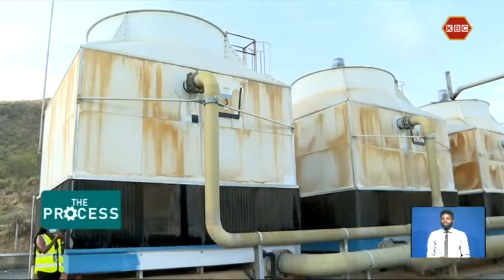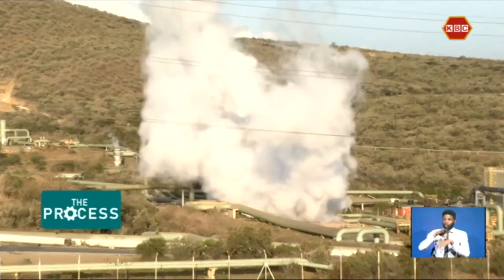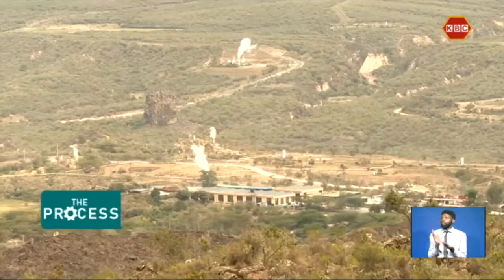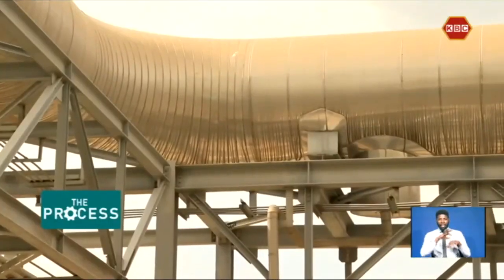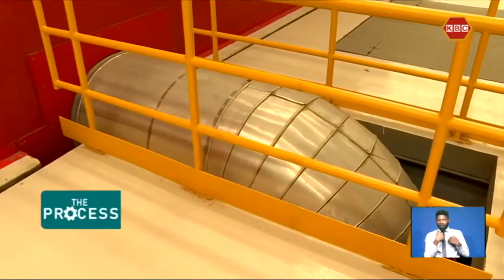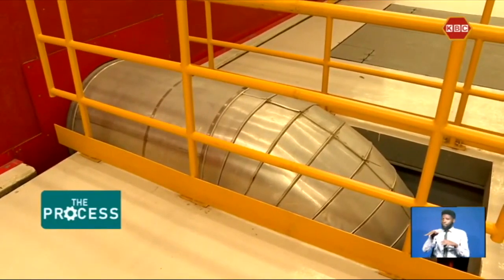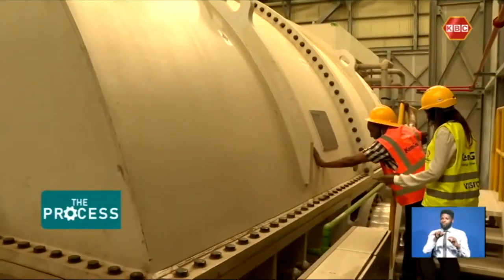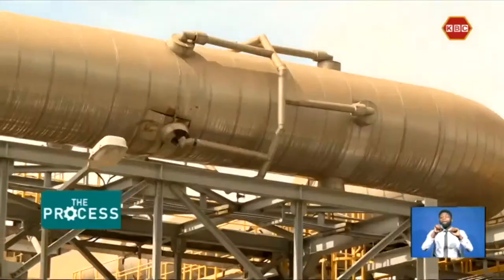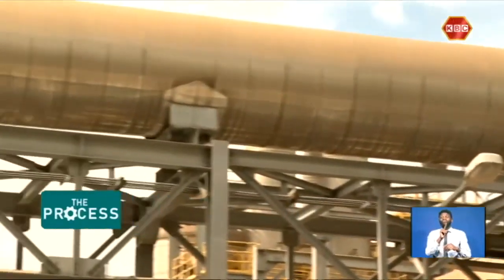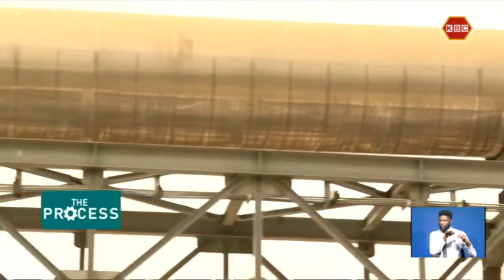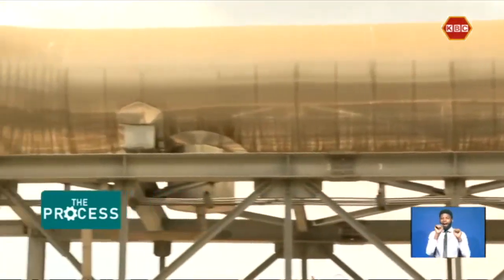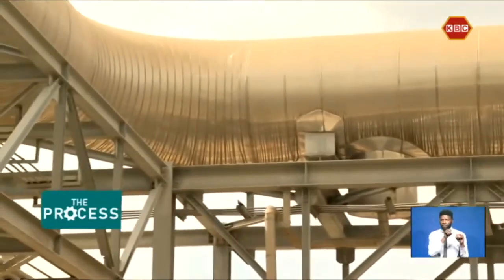The process of geothermal power making begins here. The steam comes from the steam fields through steam inlets on either side of the plant to allow the steam to flow more efficiently into the turbine. And the turbine is laid such that the steam flows from two sides so that it is very efficient. It expands very efficiently from the first stage to the last stage.